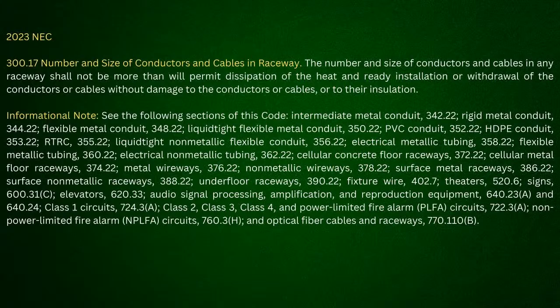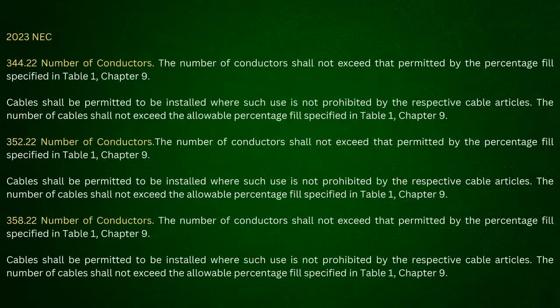Yeah. Okay. Then they put an informational note and they say, hey, go look at point 22 in all of these articles here. So I just picked out a couple, but let's see what it says. If I look at 344 rigid, it says the number of conductors shall not exceed that permitted by the percentage fill specified in Chapter 9, Table 1. Then look what it says. Cables shall be permitted to be installed where such use is not prohibited by the respective cable articles. The number of cables shall not exceed the allowable percentage fill in Chapter 9, Table 1.